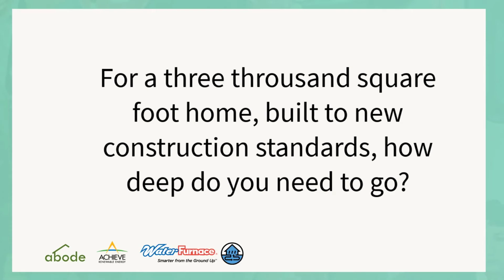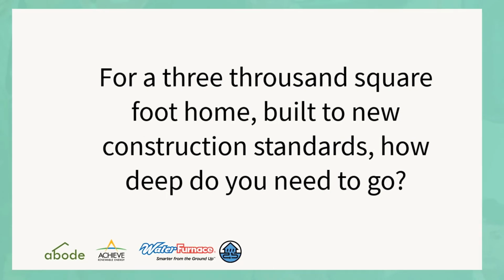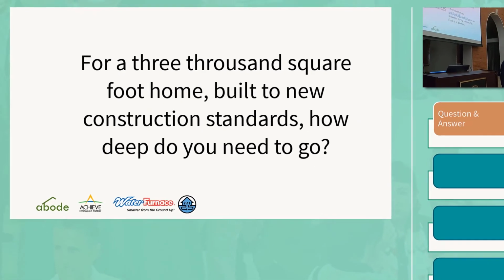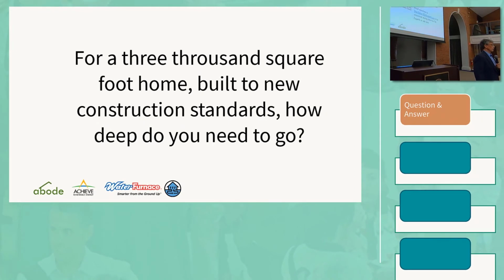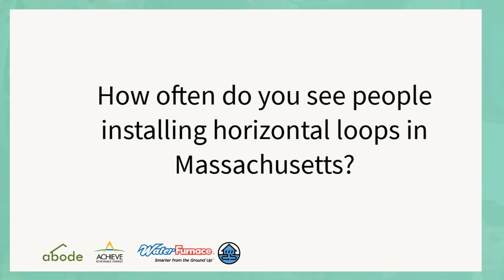Something around 600 or 700 feet of drilling, and we would normally divide that into 2 borings because the pumping overhead is less if we go through 2 borings in parallel instead of one long boring in series. About 10% of the time.